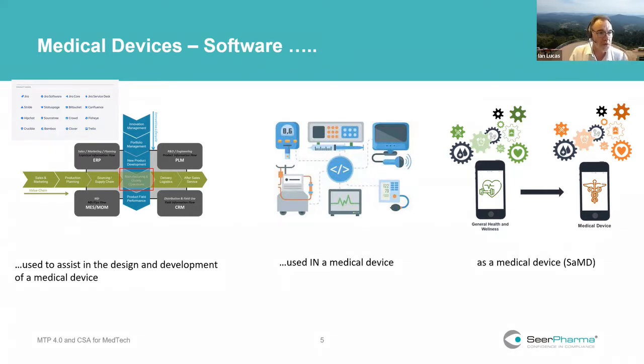So this is what CSA is all about, trying to give you back more time. And people think that CSA is about less testing. It's not. In my world, it's actually about more testing. It's about less documentation around the testing. And I've got some slides coming up that actually go through the amount of effort that we spend not on the testing, but on the actual documentation.